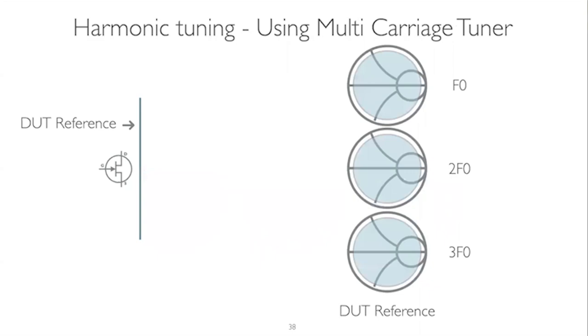So how do we do this with the MPT? Basically our philosophy was: I have a fundamental tuner, and I'm not going to cascade it. I'm going to take that probe, insert it into that tuner, and make that tuner bigger, and do the same with the 3F0. Now I get the best of both worlds, where I have a very simple setup in one tuner. I don't need to combine anything. The math inside the tuner takes care of all the calibration and the different probes, basically creating the impedances without compromising tuning range.